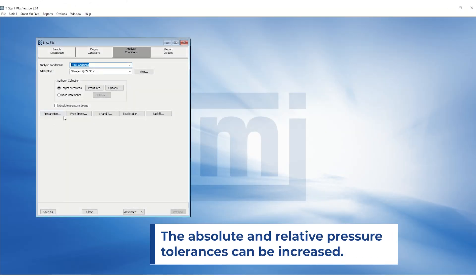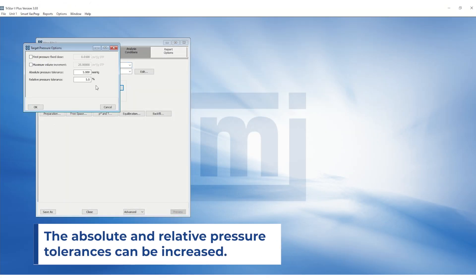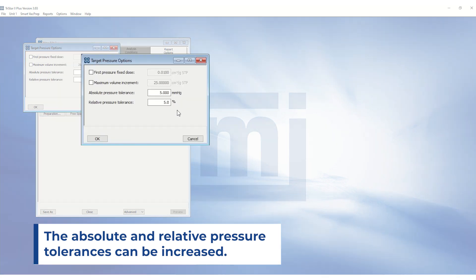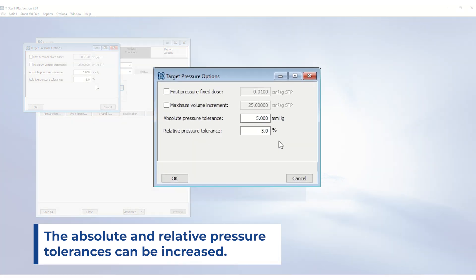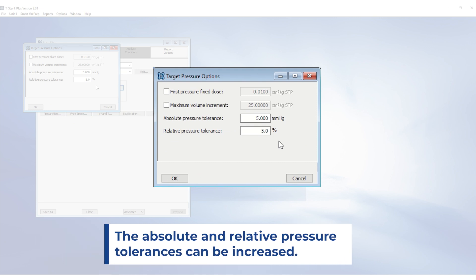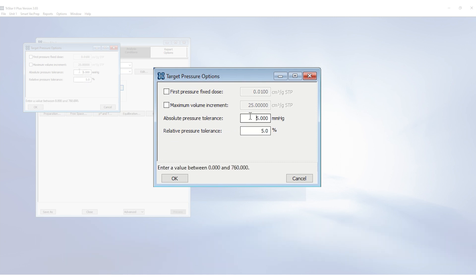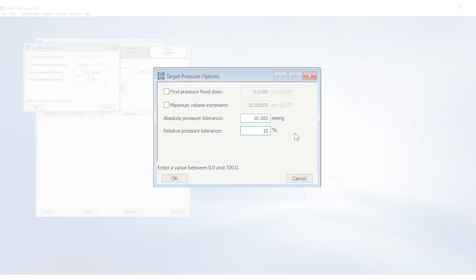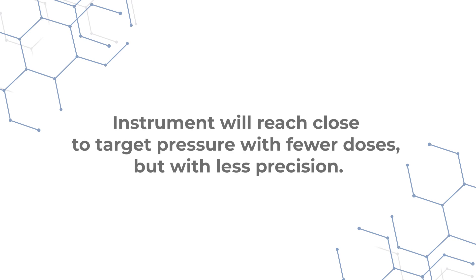The absolute and relative pressure tolerances can be increased. Typically, 5 torr absolute pressure tolerance and 5% relative pressure tolerance are used for nitrogen isotherm. These can be increased to 10 torr and 10% respectively. By doing this, the instrument will be able to reach close to target pressure with fewer doses but with less precision.